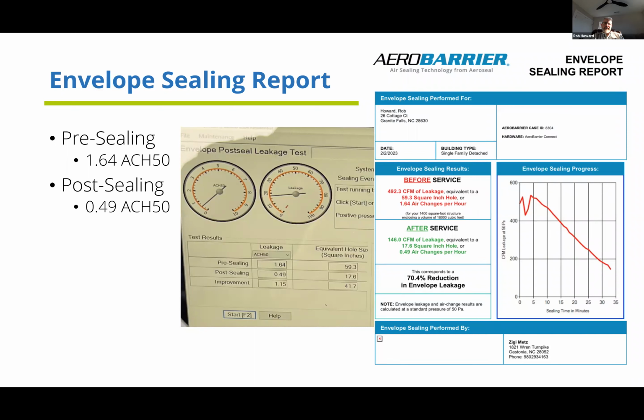The pre-sealing blower door test came in at 1.64 ACH 50. By the time they finished sealing—running the system for about 30 minutes—we got it down to 0.49 ACH 50, which would certainly meet the passive house standard. I was already pretty happy with my blower door number before they started; we did the final inspection on my house last week and came in around 1.4 ACH 50.